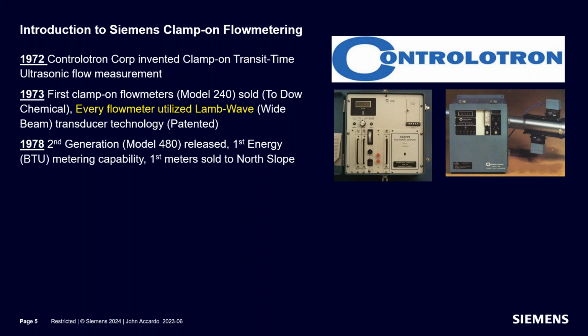And we actually created what we call the scale computer module, which was a plug-in module, and you might be able to see it here plugged into the meter, which configured the meter for the specific size pipe that you were going to measure. There was no programmability back then. So if you said you had a 6-inch schedule 40 pipe, and when you got your meter you realized it was a 6-inch schedule 80, you didn't have a meter anymore. You had to send it back and have it reconfigured. But that was the name of the game back in 1978 and 1973.